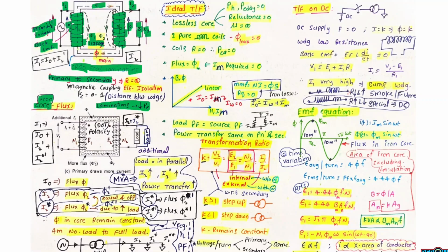Primary and secondary, these two windings are magnetically coupled and electrically isolated. So the electrical resistance between the primary circuit and secondary circuit is infinite, R equals infinity. Regarding the magnetic coupling, when the LV winding and HV winding, primary or secondary, are placed very close together along with insulation, then the coefficient of coupling can be nearly 1. If the windings are placed far away, then the coefficient of coupling is 0. This depends upon the distance between the windings.